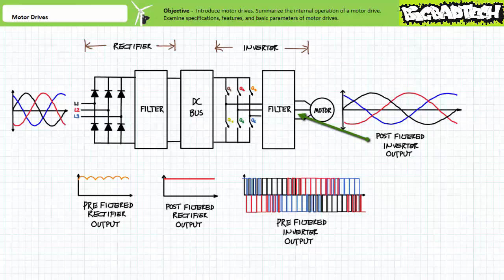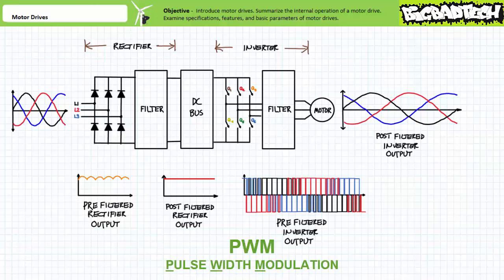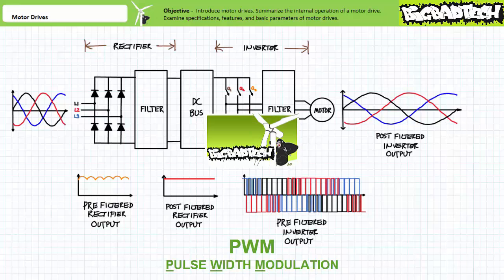The inverter can be viewed as a collection of high-speed solid-state switches that selectively connect or disconnect the DC link for various amounts of time and with a given polarity — the result being a type of pulsed output. When the filtration circuit smooths out the pulsed output, we are left with something mimicking three-phase AC, only this time frequency and magnitude are variable. This type of inversion process is known as pulse-width modulation, sometimes referred to as PWM. PWM inversion takes some explanation — we'll hold this topic for another lecture.